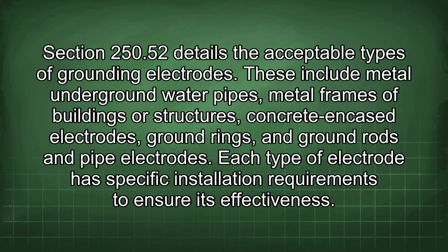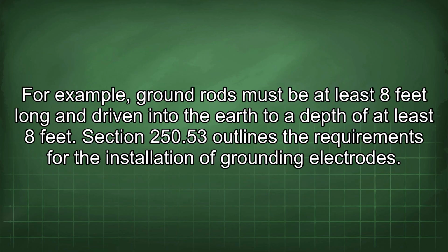Section 250.52 details the acceptable types of grounding electrodes. These include metal underground water pipes, metal frames of buildings or structures, concrete encased electrodes, ground rings, and ground rods and pipe electrodes. Each type of electrode has specific installation requirements to ensure its effectiveness. For example, ground rods must be at least 8 feet long and driven into the earth to a depth of at least 8 feet. Section 250.53 outlines the requirements for the installation of grounding electrodes.